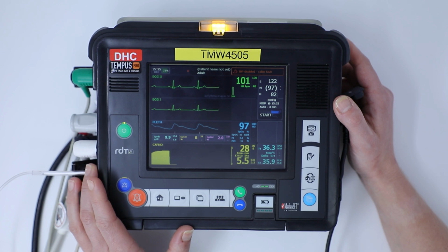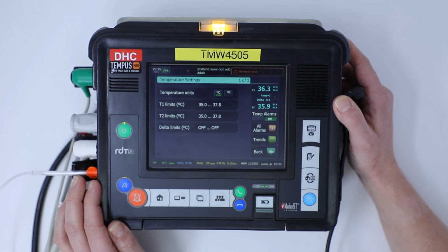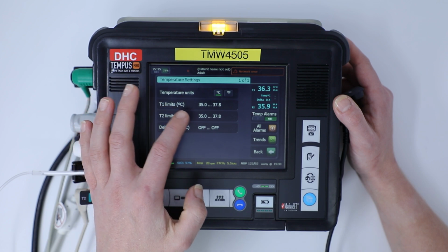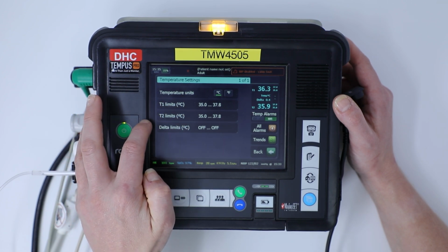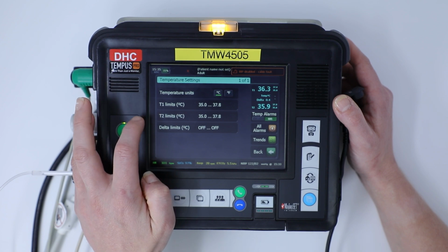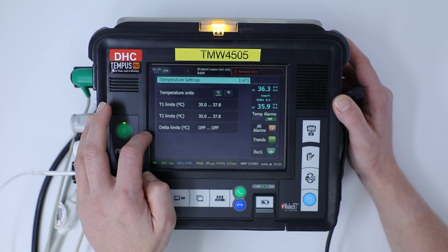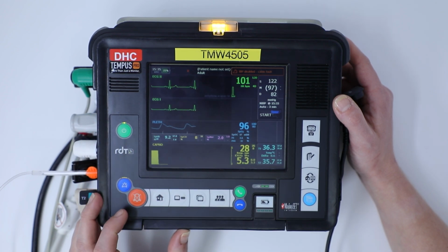Okay, looking at our temperature parameters, again, we're going to click on the temperature box in green, and it's going to give us the options for what we can adjust. So we can look at the temperature units in degrees Celsius or degrees Fahrenheit, and we can look at our 2 temperature port limits and set a lower and an upper threshold for when it'll alarm, as well as our delta limits.